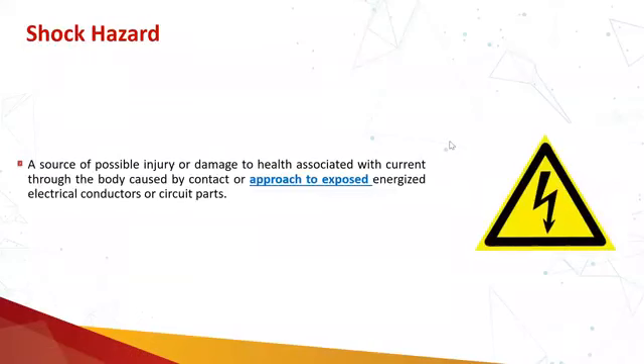So quickly going through the definitions given in Article 100, what is a shock hazard? A possible source of injury or damage to health associated with the current through the body caused by the contact or approach to exposed energized electric conductor or circuit part. So electric shock is not received only when I'm coming in contact directly with the energized electric conductor or circuit part.